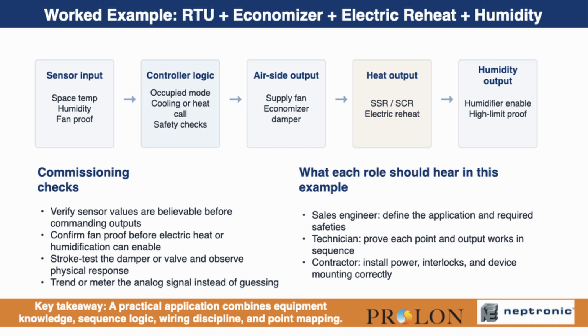Second, what sensors tell the controller what is happening? Third, what outputs can the controller command? And fourth, what safeties or interlocks can prevent normal operation? In a case like this, the controller may decide when to bring in outdoor air, when to call for cooling, when to energize reheat, and when to manage humidity.